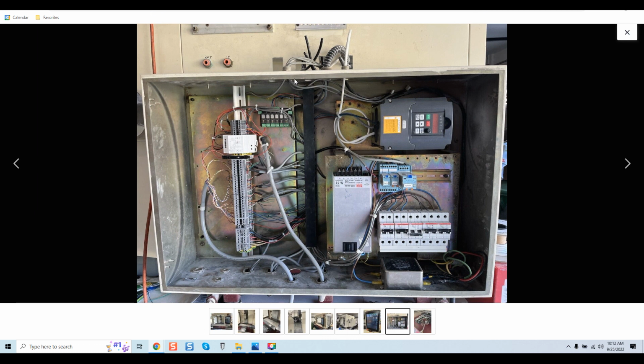First of all, we see ports that are open in the electrical enclosure, which means that once you have those ports open, if you don't seal them, you're going to get dirt and debris in here. He's reusing this enclosure. I feel for this price, he could at least have cleaned it, emptied everything out, painted it, or at least sealed it in some aspect and form, used some proper glands to have pass-throughs from the enclosure.